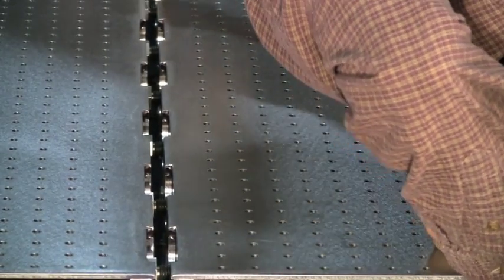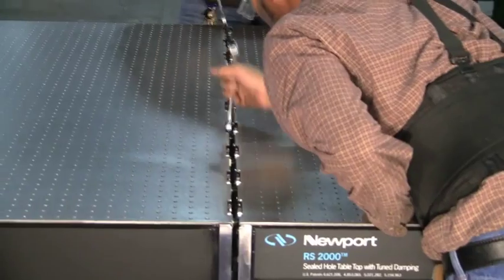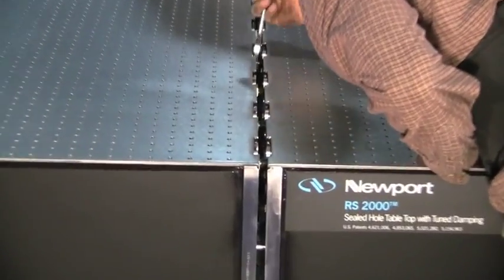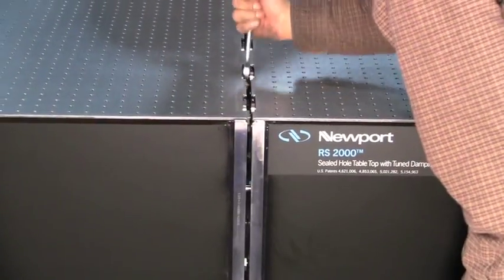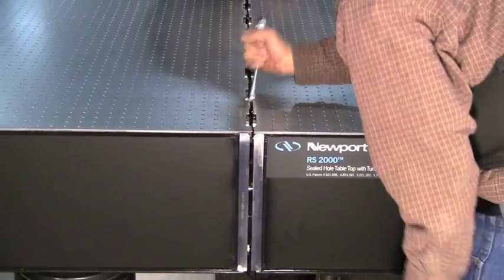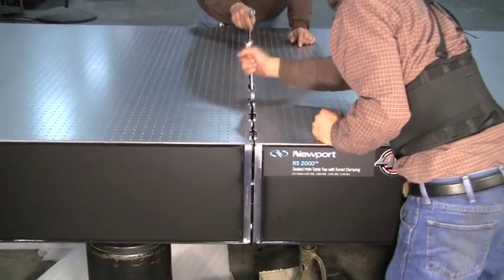This is an iterative process to ensure the two table sections are drawn together as parallel as possible along the top and bottom. This gradual tightening will also help prevent damage to the threads and prevent the bolts from binding.